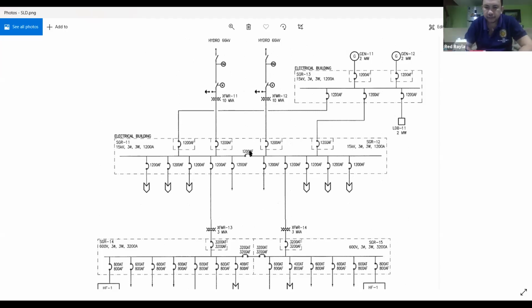Breakers at the switchgear would remain open so that the transformers are first energized and allowed to soak for a 24-hour period. This is similar to factory acceptance testing, where now that it's in the field, transformers are energized and allowed to thermally stabilize to confirm there's no thermal hotspots or corona discharge. You likely take an oil sample before energizing and after energizing. You can measure the oil sample to confirm if there's any off-gassing or hotspots within the transformer. That 24-hour soak period is important to confirm that the transformer is operating stable before proceeding with any downstream energization of the systems.